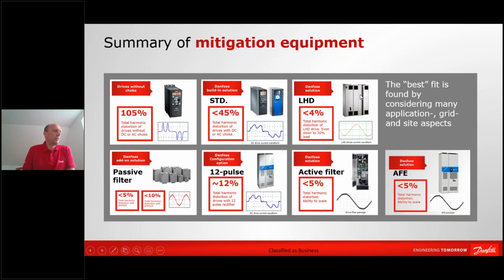Then you can add low harmonic drives, which is a combination of a drive and an active filter. It goes as low as 4% current distortion. It brings you almost a sinusoidal current waveform, and that could actually be a quite neat solution when you have a very high demand for mitigation. It has the benefit of being very stable for imbalances on the grids. It has a benefit of actually having the ability to disconnect the filter, so the drive is only running when the mitigation is not needed, which could give you higher energy efficiency, and some other benefit of that solution.